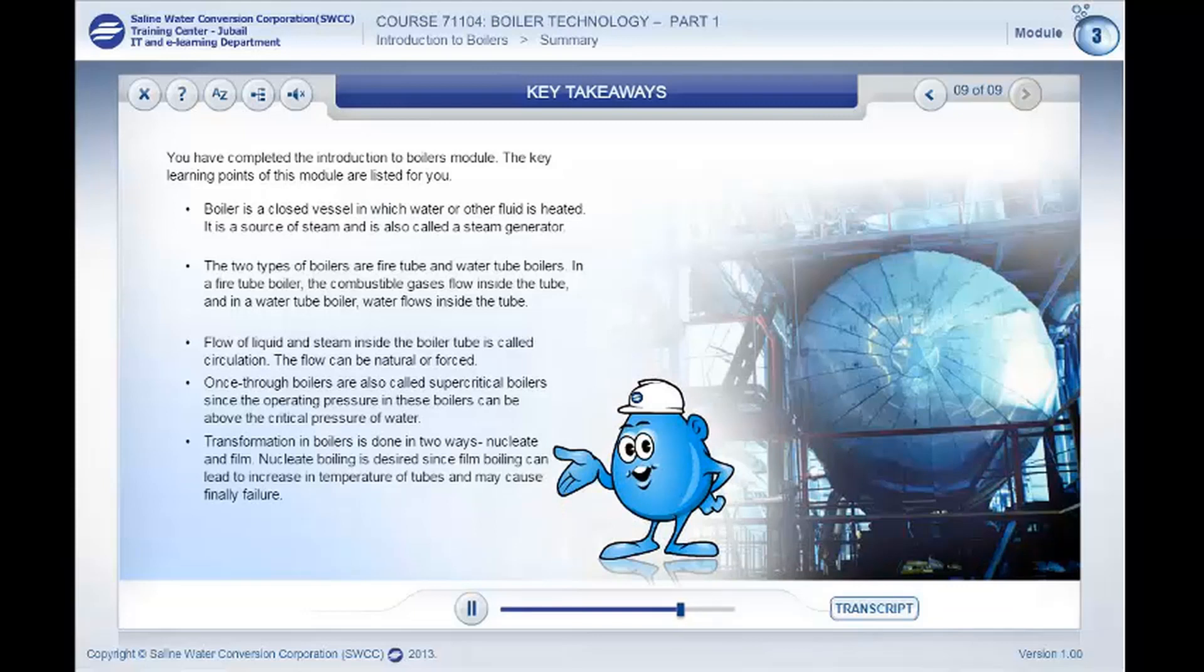Transformation in boilers is done in two ways, namely, nucleate and film transformation. Nucleate boiling is desired since film boiling can lead to increase in temperature of tubes and may cause failure.